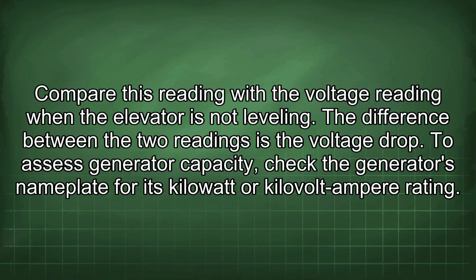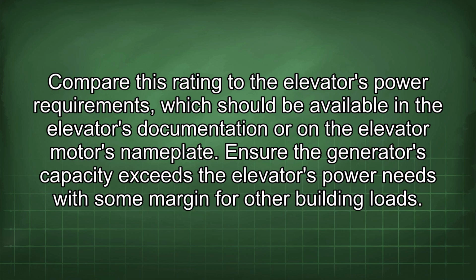To assess generator capacity, check the generator's nameplate for its kilowatt or kilovolt ampere rating. Compare this rating to the elevator's power requirements, which should be available in the elevator's documentation or on the elevator motor's nameplate. Ensure the generator's capacity exceeds the elevator's power needs with some margin for other building loads.